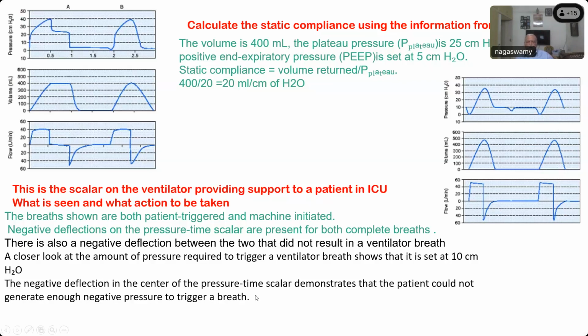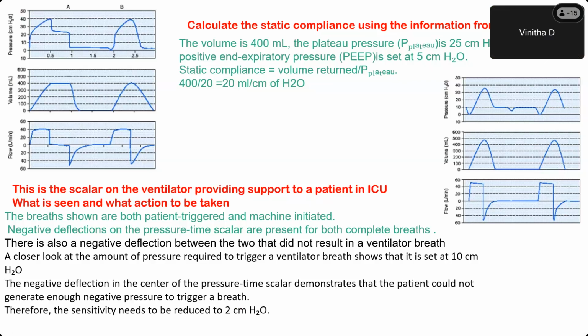So what should you do? You should reduce the sensitivity. So from 10 centimeters, you reduce the sensitivity to 2 centimeters of water. Then the machine will support his breath and the patient will be getting a full machine breath also. So the main action to be taken is to reduce the sensitivity to the inspiratory negative deflection. This is a spontaneous breath. Okay.